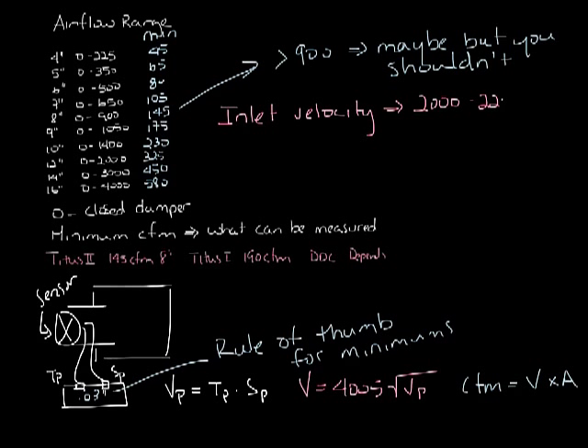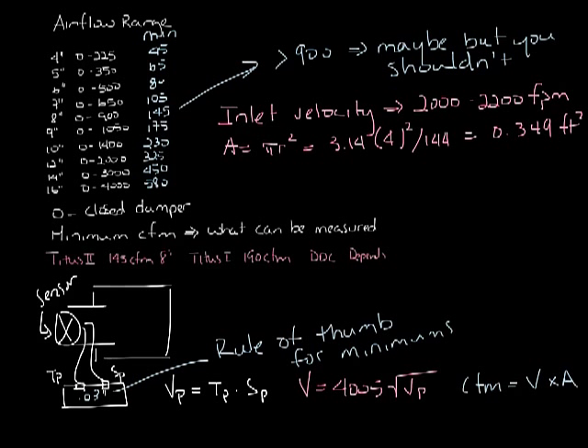Ideally, you'll want to keep the velocity through the inlet around 2,000 or 2,200 feet per minute. So let's look at that 8-inch box again. The area of the 8-inch box is pi r squared, which is 3.14 times 4 squared, divided by 144 to get into feet. That's 0.349 square feet.